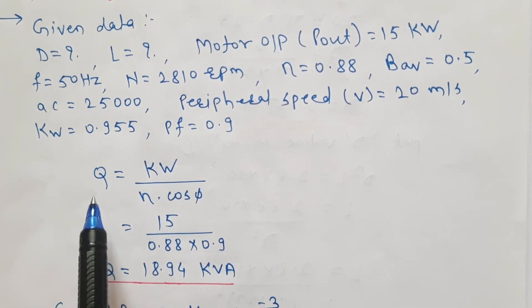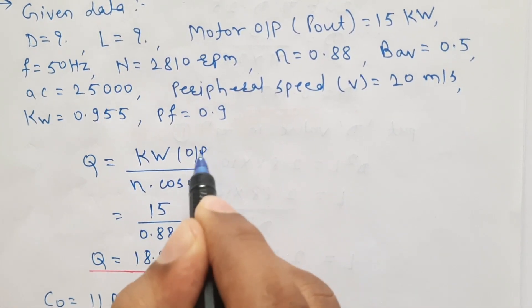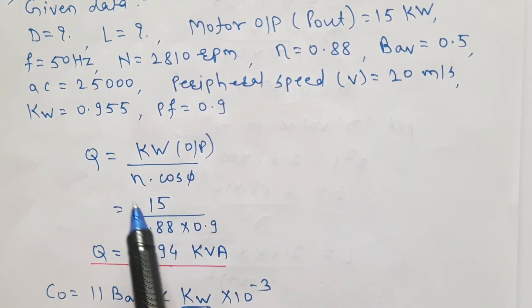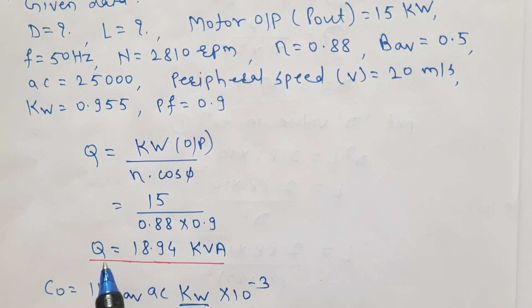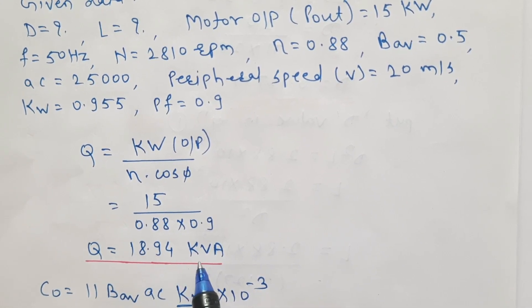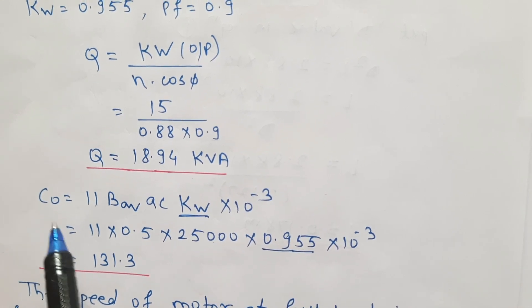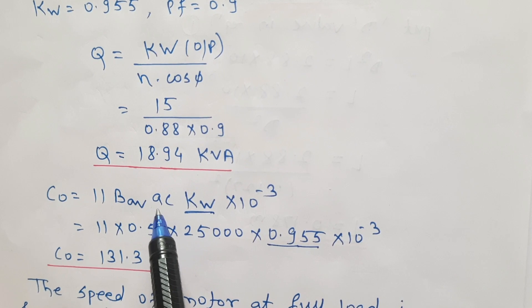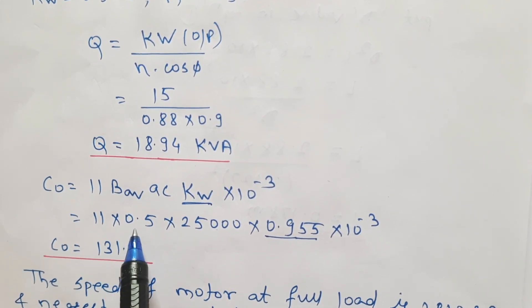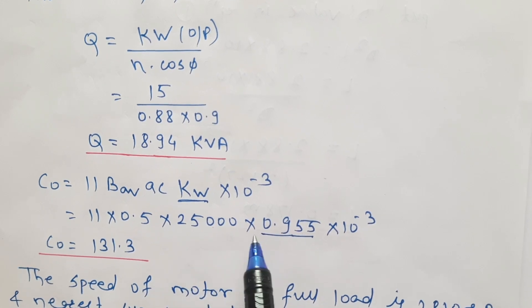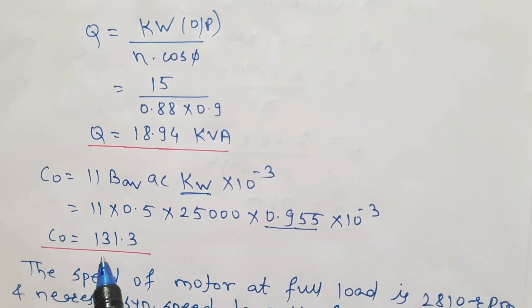Now solving: Q equals input rating in KVA equals KW divided by efficiency into cos phi. Motor output KW is 15 kilowatt, so Q equals 15 divided by 0.88 into 0.9, which gives Q equal to 18.94 KVA. Second step, the output coefficient C0 equals 11 times B_AV (0.5) times AC (25000) times Kw (0.955) into 10 to the power minus 3, which equals 131.3.